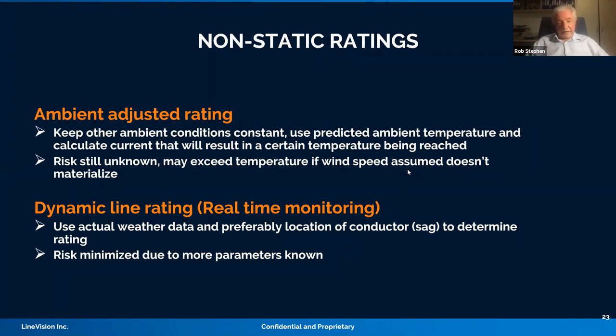And the beauty about ambient is that it is fairly accurate, and the projections per hour over the days are fairly accurate, unlike wind speed, especially low wind speed. Your risk, though, is still unknown, and you may actually exceed your design temperature if your assumed wind speed doesn't materialize. This is particularly important if you've assumed a very high wind speed in your deterministic ratings. For example, if it's around 2 feet per second or higher, the probability of that being reached all the time, especially in the evening, may not be realized. So you might have a risk there which you do not really understand unless you do some further analysis. So you can use the ambient adjusted rating, just be aware of the risk.